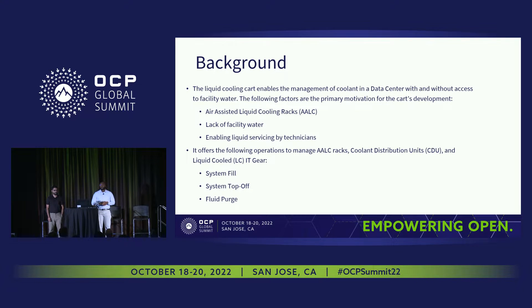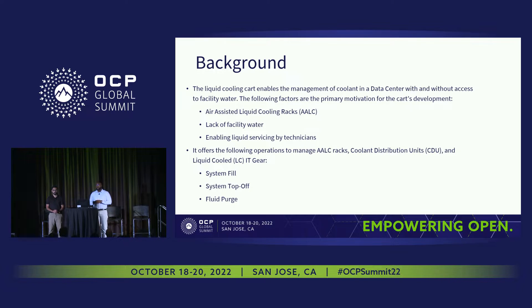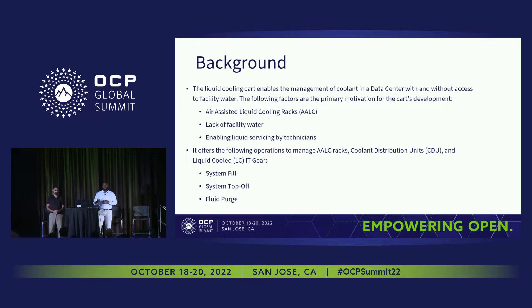Why are we designing a liquid cooling cart? This is because of the lack of facility water in our current data centers. In order to use liquid cooling for our IT-enabled gear, we need to use what's called an AALC, or air-assisted liquid cooling rack. This prompted the need for a cart so that we could service the AALC rack when it's in our data center. Its primary functions are to fill, top off, and purge the rack.